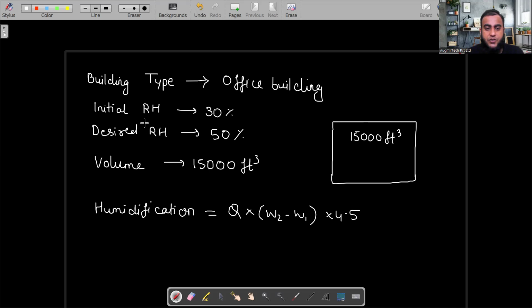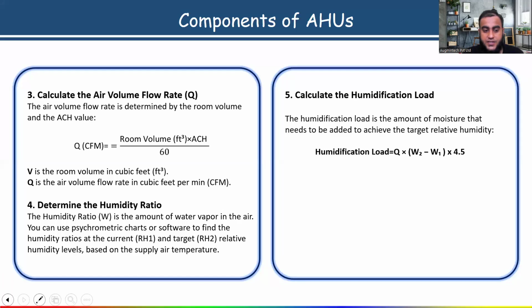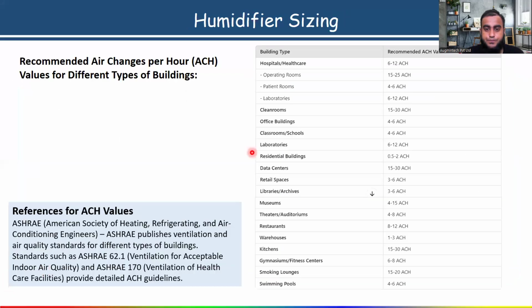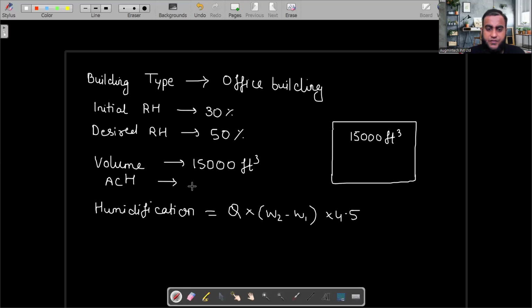So if you know the initial relative humidity, desired relative humidity, and volume, the ACH is important. Let me know, for an office building, how much ACH, air changes in 1 hour? How many times do we have to change the air? If you see, it is given for office building 4 to 6. Let's say I'm considering 6 maximum. Better is to consider the average one, 5. So in my calculation I'm considering 5, from that table.